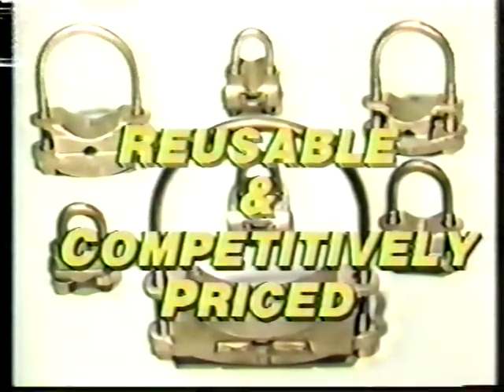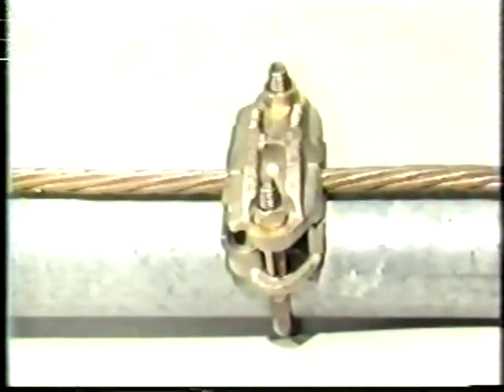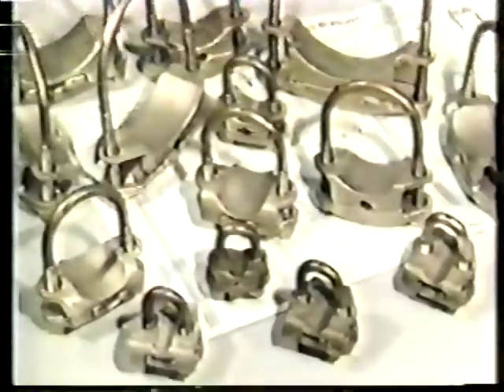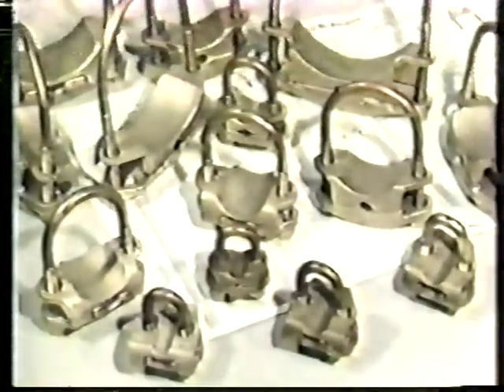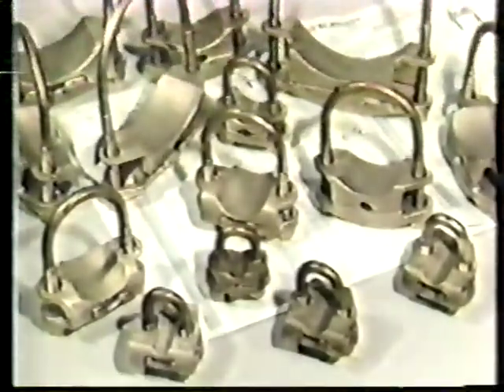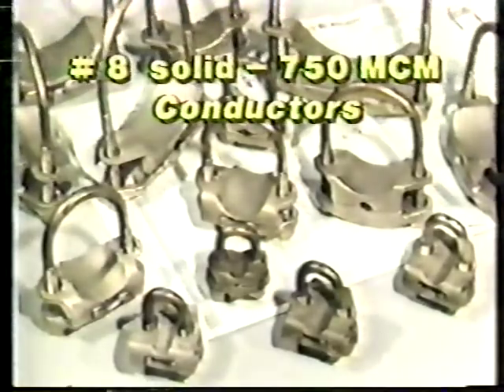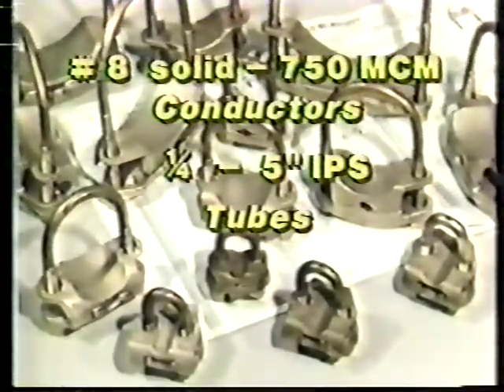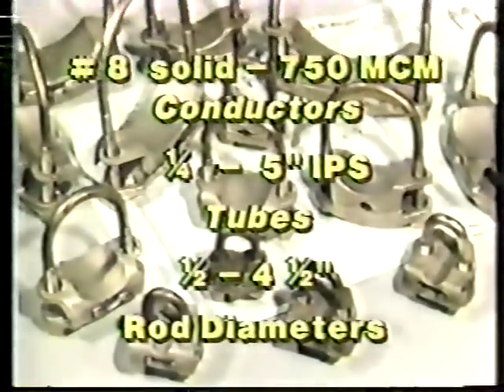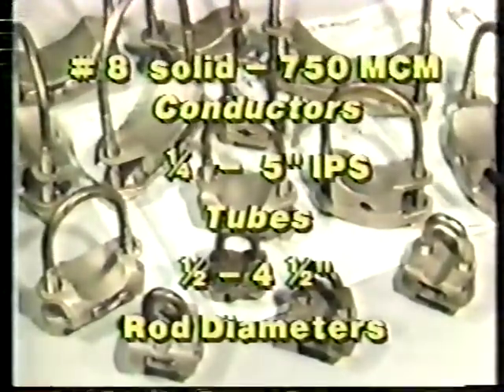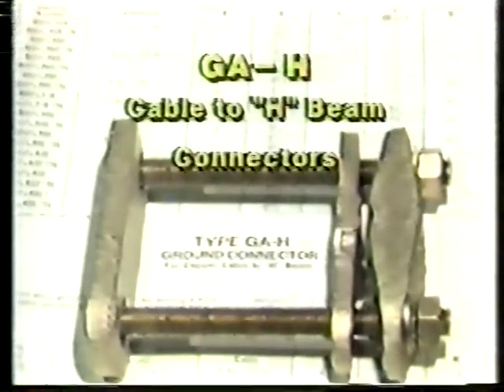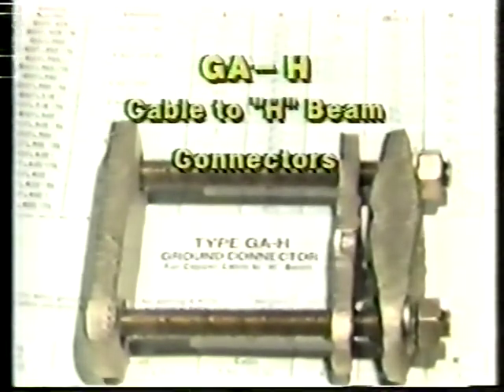The GAR ground connectors feature one wrench installation, and they'll reduce your inventory because the same connector can be used for both parallel and perpendicular cable-to-pipe installations. As with most of Burndy's connectors, these devices are range-taking and available to accommodate number 8 solid through 750 MCM conductors, tubes ranging from 1/4 inch to 5 inches IPS, and rods of 1/2 inch through 4.5 inches in diameter. Versions to attach cable to H-beams or square tubes are also available.